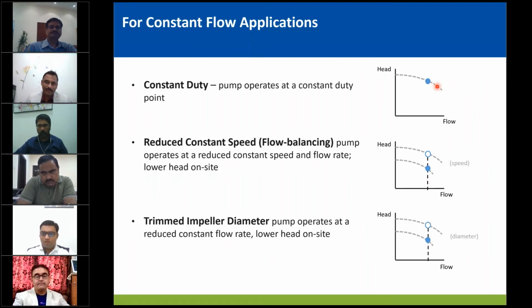So traditionally we would install a throttling valve and create head and throttle the pump back on the curve to the design point. This is to ensure pump reliability over years of operation. So it should operate in the right best efficiency area, and it should also not consume higher power and overload the motor or run into bearing issues in the pump. But the throttling valve is an investment, and by throttling, we are also wasting energy because it's creating head which is not required in the system.